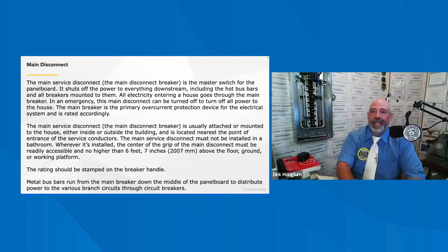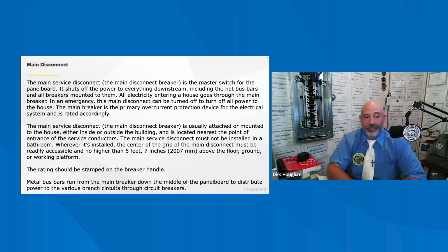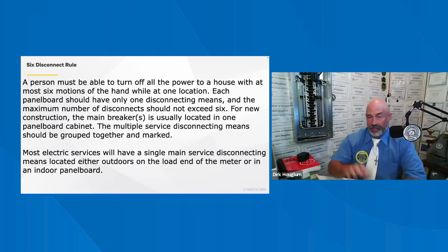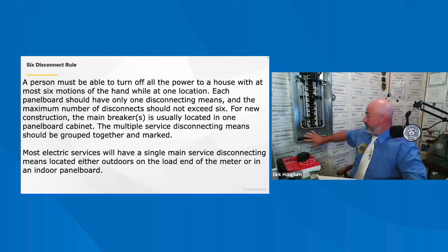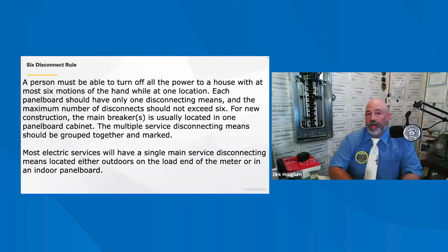Okay. In the NEC, 230.70, the main disconnect, outside or inside the home, has a minimum height that varies by jurisdiction. It has to be readily accessible. NEC 404.8, we already talked about the clearance in those types of areas, and we've kind of covered everything that this is talking about. One of my big call-outs in a lot of home inspections is that there's not enough clearance around this. This would not be acceptable if this was mounted here because I have this in the way. I don't have my 3-foot clearance. A person must be able to turn off all the power in the house with minimal motions of the hand, and it says 6 motions is what's recommended.